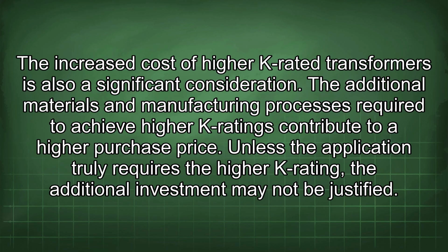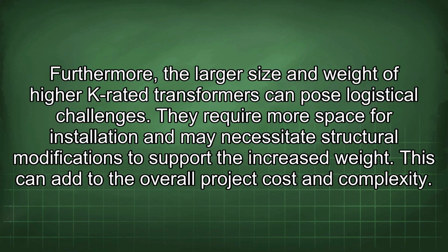The increased cost of higher K-rated transformers is also a significant consideration. The additional materials and manufacturing processes required to achieve higher K ratings contribute to a higher purchase price. Unless the application truly requires the high K rating, the additional investment may not be justified. Furthermore, the larger size and weight of higher K-rated transformers pose logistical challenges. They require more space for installation and may necessitate structural modifications to support the increased weight. This can add to the overall project cost and complexity.